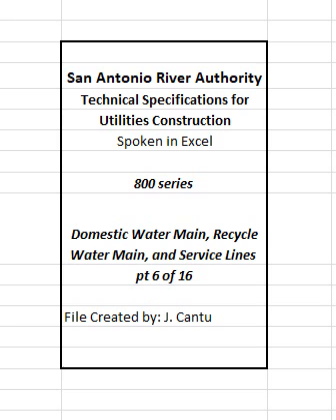V. High-density polyethylene, HDPE, pipe and fittings. 1. High-density polyethylene pipe and fittings. All pipe and fittings shall conform to the same requirements as those specified for HDPE pipe and fittings. All HDPE shall have a minimum pressure rating of 160 psi and a minimum dimension ratio of 11, DR 11.